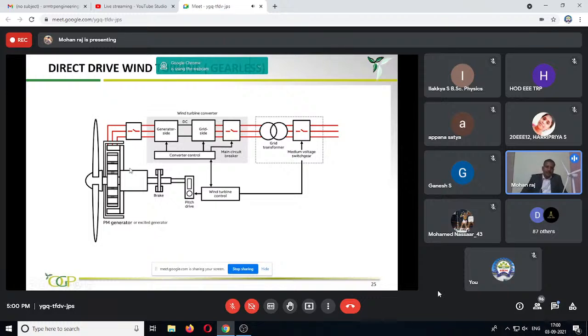for conversion. You see, this is the rotor, and permanent magnet generators or excited rotor generators are used in the direct drive wind turbine. Further, there is one circuit breaker for protection of this generator, and then on the generator side, there is a converter available. This converter will convert the variable alternating current, variable voltage and variable frequency, to variable direct current. So this is a rectifier. Normally it is called a rectifier, which converts alternating current to direct current. But the alternating current generated by the direct drive turbine is variable in nature, and it is converted to variable DC. Further, the DC choppers are used, step-up choppers and step-down choppers, which you studied in the power electronics subject.